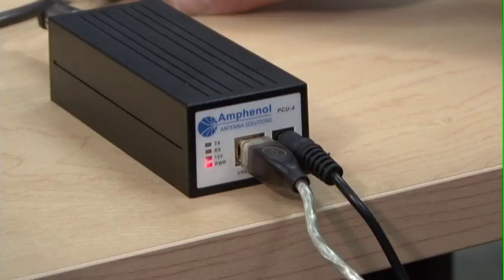A dim or flickering LED may indicate a DC block in the system, primarily if smart bias-Ts are being used. Check the coaxial jumper and feeder system to make sure there are no devices, such as lightning protection or circulators, that will block DC current from the controller to the RET antennas.